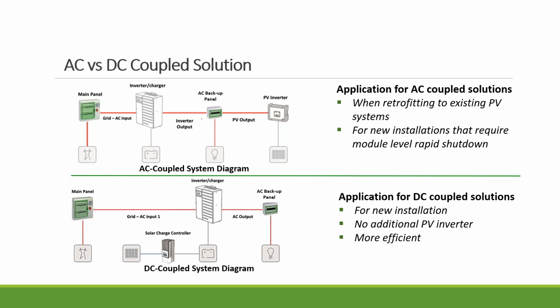Now, an AC coupled system is where you have a solar array connected to the PV inverter. It could be a microinverter, it could be a string inverter, it could also be an optimizer plus string inverter, like a SolarEdge inverter here. It connects to the essential load panel or backup panel. Then you have a hybrid inverter also connected to the essential load panel, as well as to the main panel and to the grid. So the battery is connected on the AC side, as you can see, right? Because the power from the PV inverter is converted from DC to AC and travels through two inverters, and then the battery is hooked to the AC side. Of course, when the inverter is discharging the battery, it will convert from DC to AC. So that's called an AC coupled system.